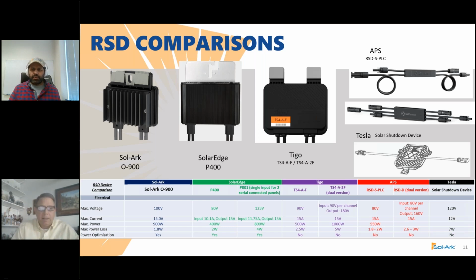Third party, you've got Tigo. The reason Tigo works with us, much like the APS sitting next to it, is that they provide their own transmitter. As you saw in the previous slide, the transmitter is powered from an AC power supply, and the working end of that transmitter goes around the PV input wires that come from the Tigo receiver. That system is all sort of self-contained - Tigo provides the transmitter and receivers, and as long as that's working, the Sol-Ark accepts the power from the solar panels and everything works like normal.